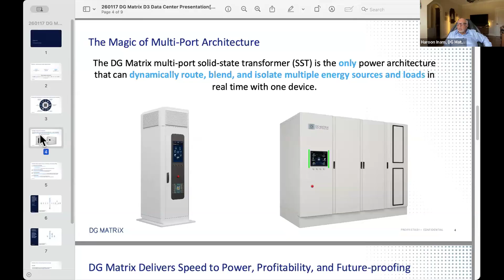DG Matrix's multi-port solid-state transformer is the only architecture that can seamlessly blend multiple AC and DC sources, such as fuel cells, natural gas gensets, diesel gensets, batteries, or any other AC or DC source with the grid, and blend it in thousandths of a second or faster to mitigate pulses and provide much more power behind the meter, cheaper. Our solution is 1/2 to 2/3 the TCO of any other competitor just by the CapEx alone, not to mention we have higher efficiency with far fewer components in the delivery chain.